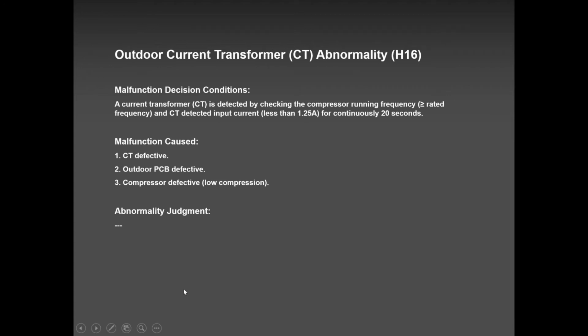H16. I had an H16 on an 8-9-year-old unit, a very old unit, probably more than that, because it was an R22 inverter system, and it had an H16, and it was the compressor pumping. The pumping was not good. So it could be the outdoor PCB or it could be low compression. But in my experience, on a few calls on H16, the compressor pumping was low. Okay, so you never know. In your case, it could be the compressor or it could be the outdoor PCB.